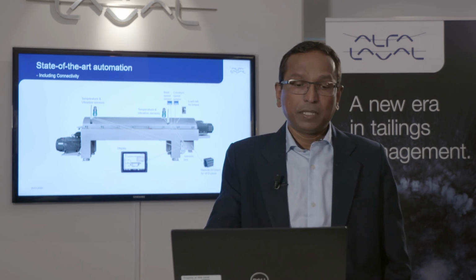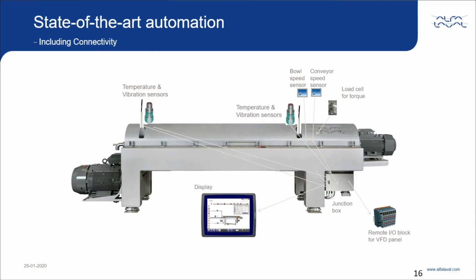And this slide now shows the state-of-the-art automation that is being used for all Alfa Laval solid bowl centrifuges. There are bearing temperature sensors on both the conveyor bearings and on both the bowl bearings, and we have bowl speed sensors and a conveyor speed sensor. There's a load cell for calculating the torque and keeping it under control.